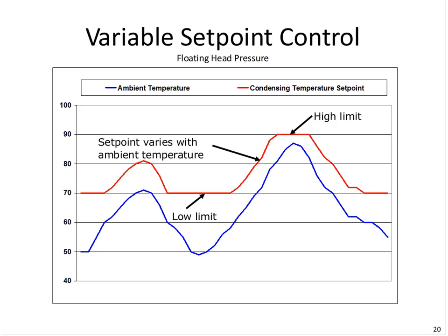Here's a day or 2 days in the life of floating head pressure. What we've got is the ambient temperature, the bottom blue line here, and then the red line is the condensing temperature. So we're starting at nighttime through the heat of the day, and then nighttime again, and here's the second day. We just want to portray how this might control. So if the ambient, say, is down at 50 degrees, and we may have a low temperature control set point of, say, 70 degrees, and quite often that's due to oil separation. We might be able to get down to 60 degrees, but because of our equipment, maybe we're prohibited from that. So we would just run the variable speed fan to attain an actual condensing temperature of 70, even though our ambient might be down here at 50.